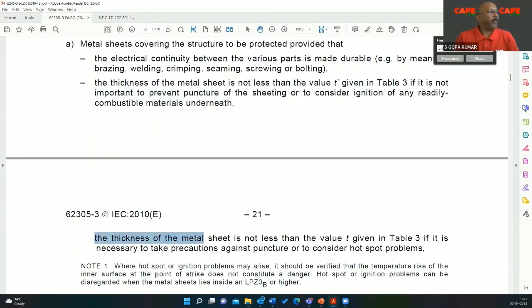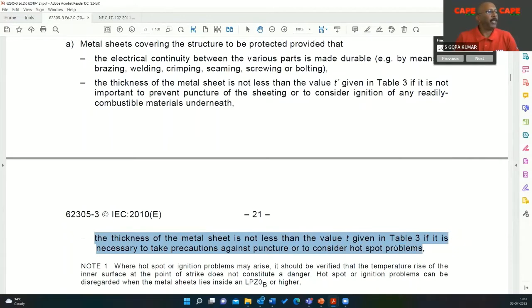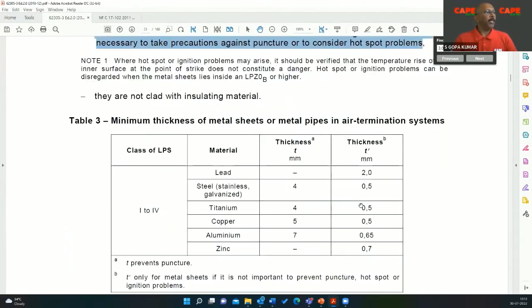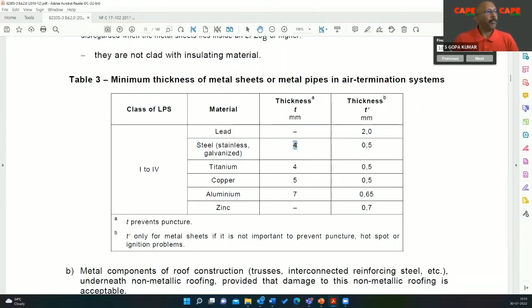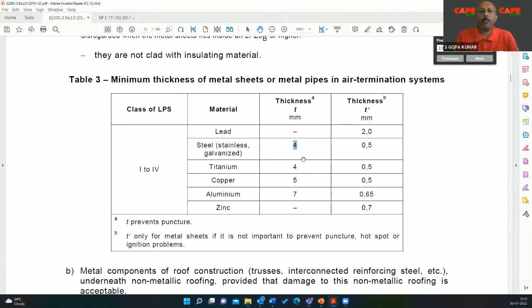The thickness of the metal sheet must not be less than T given in the table if it is necessary to take precaution against puncture or to consider hot spot problems. In this particular case, we don't use lead or titanium — we use galvalume sheet or stainless steel. If the thickness of the metal is more than 4 millimeters, which is rare and used sometimes in oil storage tanks, lightning cannot puncture this material.